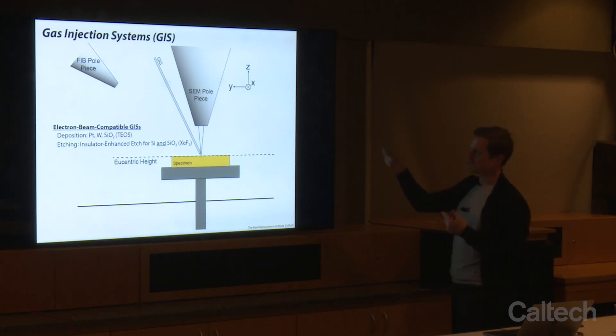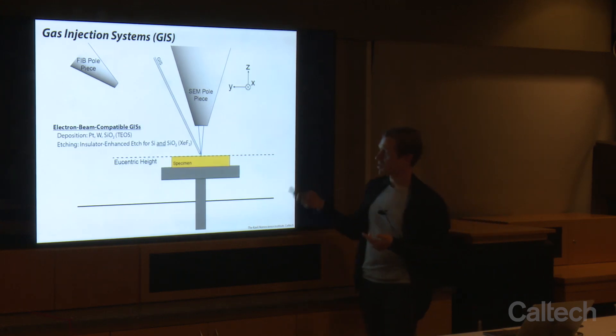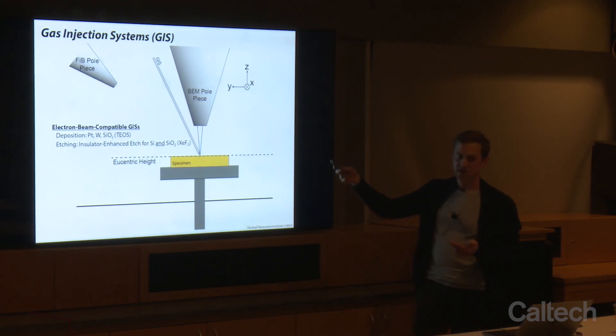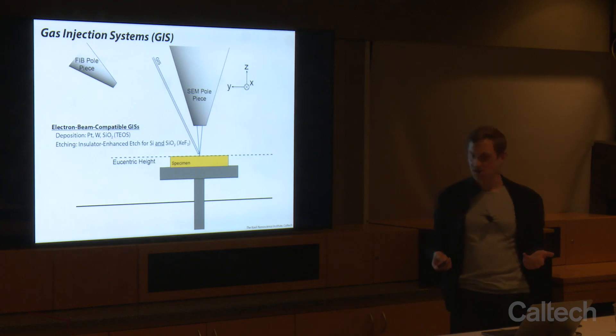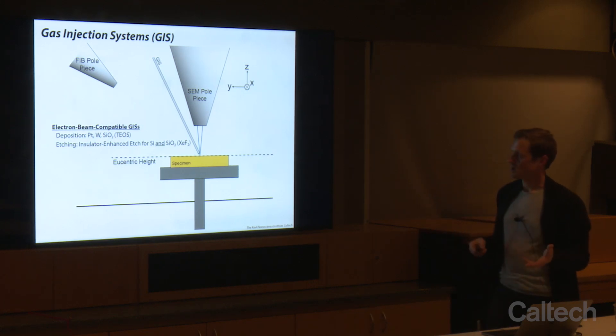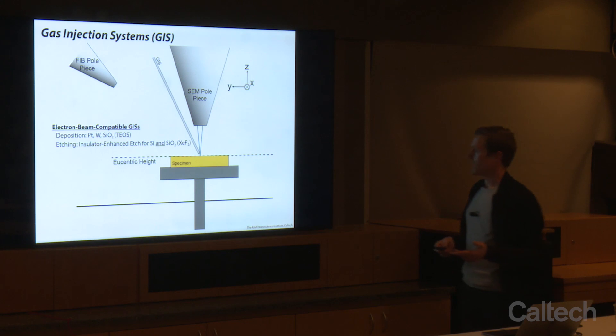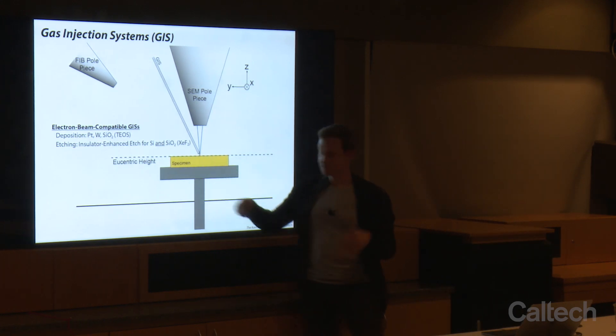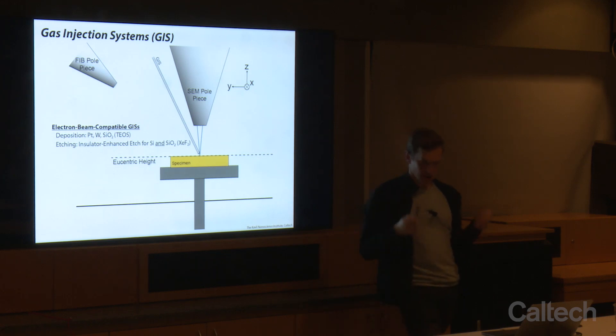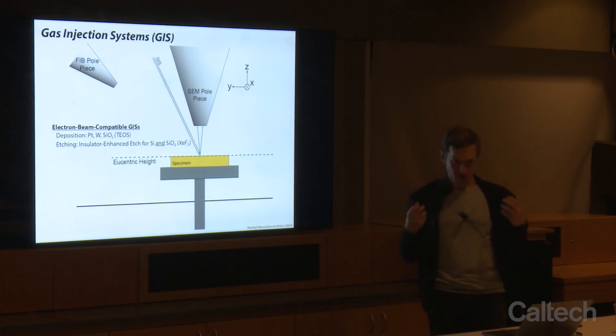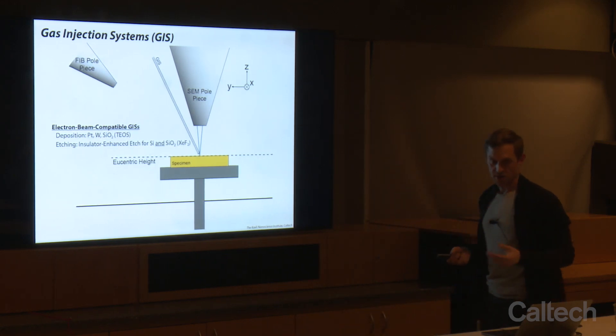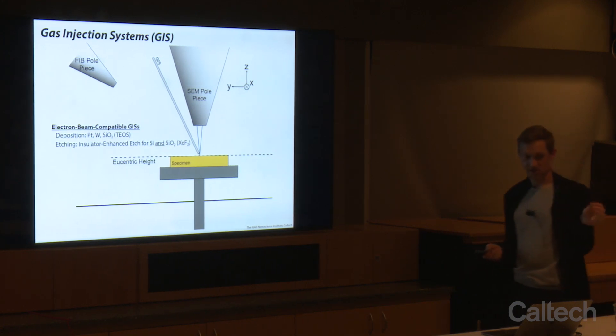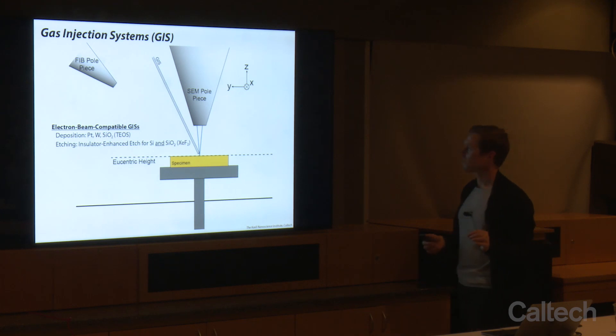We can also use these gas injection systems with the electron beam. Primarily we do this to deposit material — platinum, tungsten, and silicon oxide will all deposit the same way as with the gallium beam. We can also sometimes do etching: people have reported that with xenon difluoride gas and incident electrons adding energy, you can enhance the etch rate of your material just with the xenon difluoride and electrons.